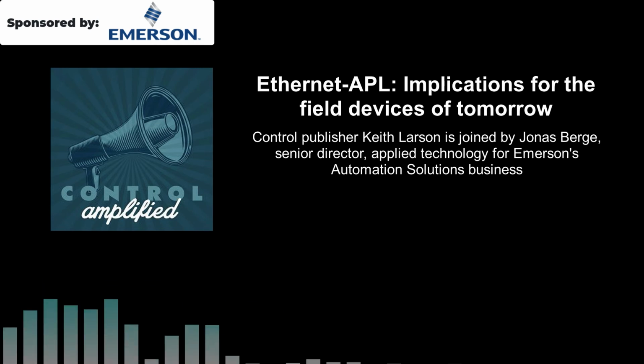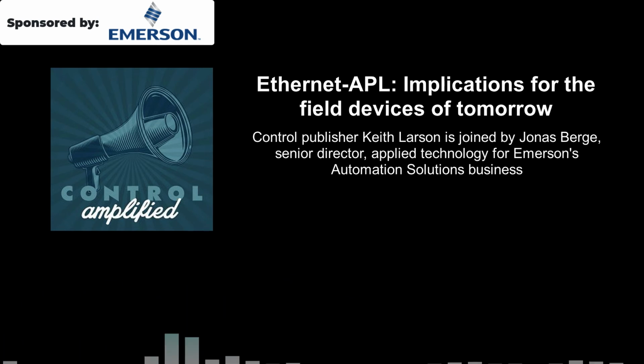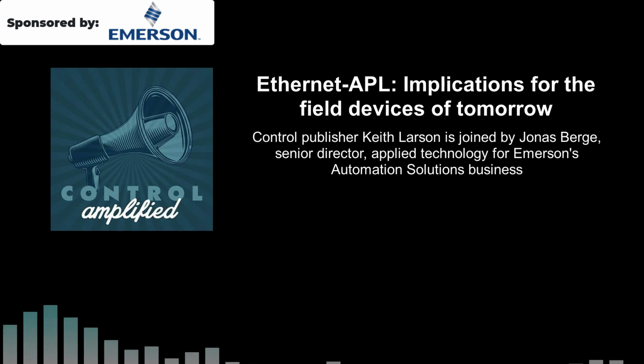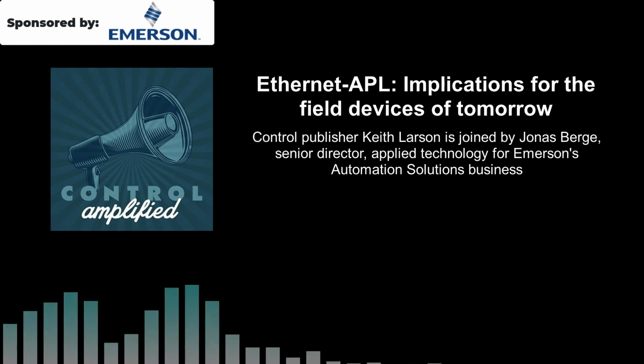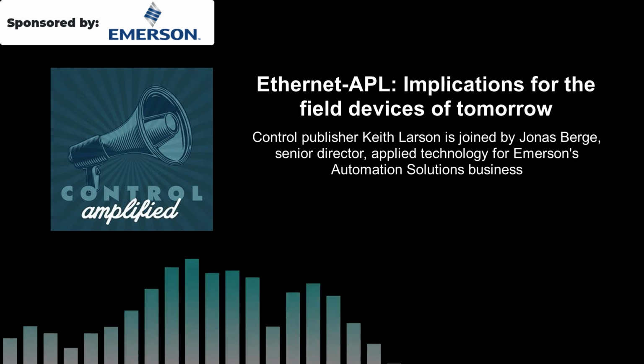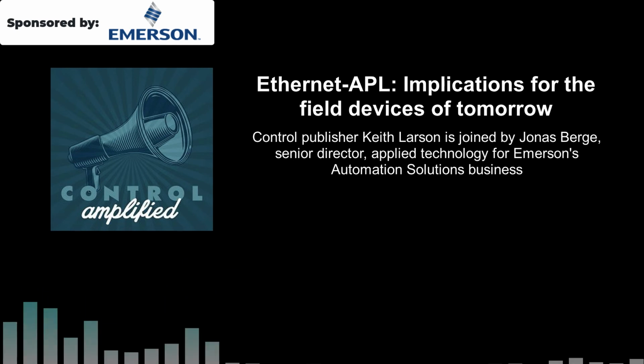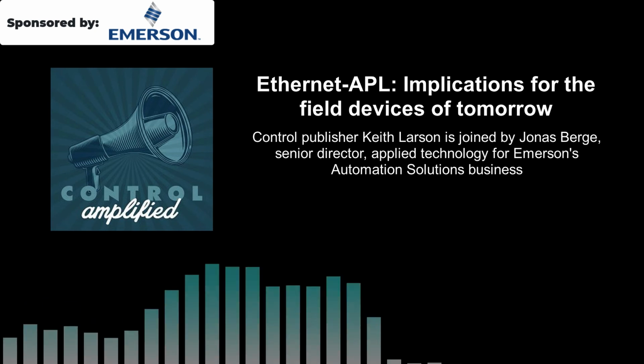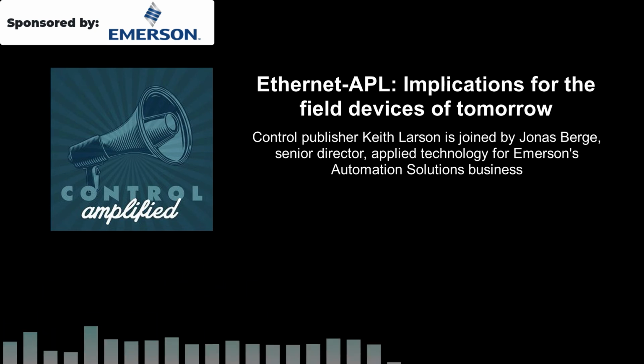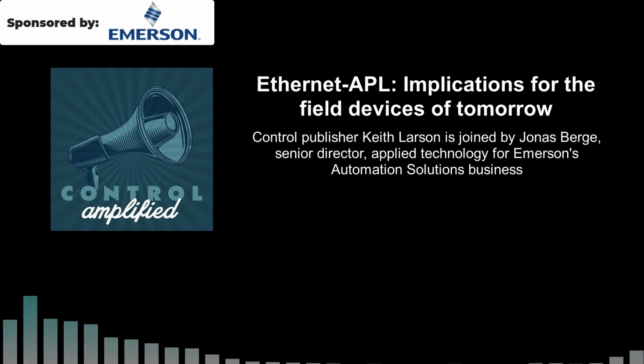So it becomes a lot easier to manage this mix of instrumentation if APL devices use HART-IP, because HART-IP, 4 to 20 milliamp HART, and wireless HART are all HART. They all work and look and feel the same way. This makes the job of instrument engineers and technicians so much easier, because so much functionality and terminology is common.